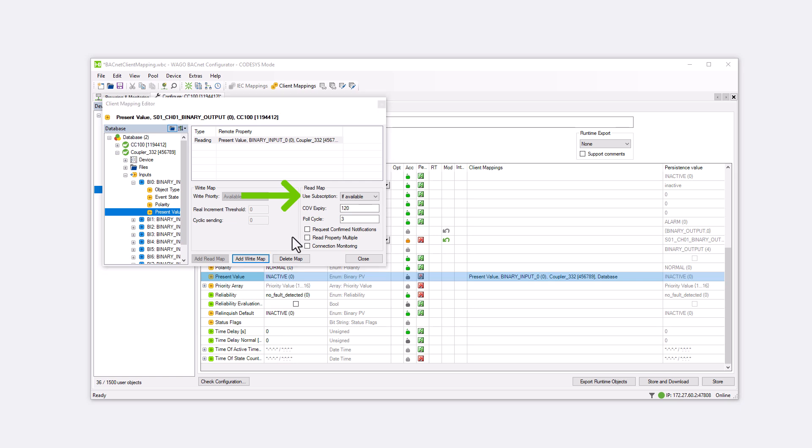In the Use Subscription field, we can select the method. Always uses COV exclusively, while never uses only polling. If available, first attempts to subscribe to the value on the server by sending a subscribed COV telegram. If this fails, polling is used.